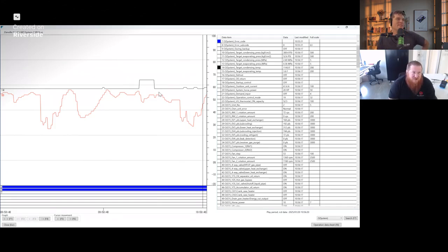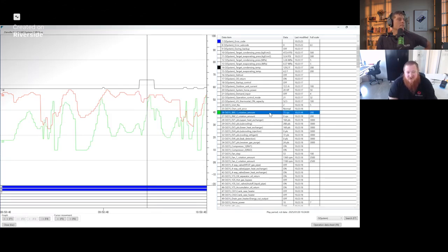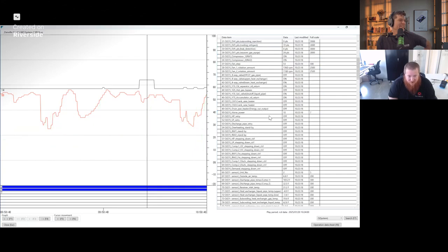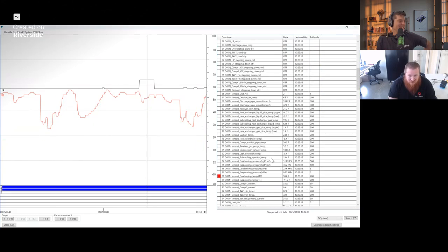If you take, for instance, test operation, and we look at our targets in test operation. One of the biggest no-nos about sending data to somebody to analyze is don't send them test operation data. It is the worst data that machine will ever display in its entire life. The point of test operation is to help the machine set the targets, but in that instance, it drives the targets to the gutter.